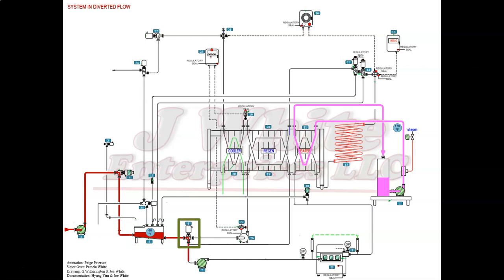The regenerator bypass valve is de-energized and feeds the stuffing pump when in diverted flow. The stuffing pump feeds the homogenizer/timing pump at the required flow and pressure to ensure no air leaks into the cylinders on the suction stroke.